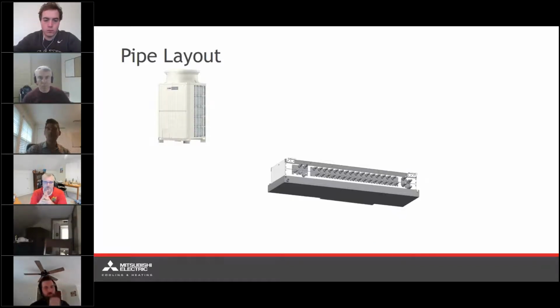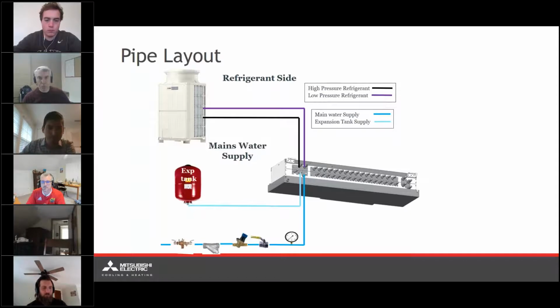All right, so this is just going to go through some of the components that need to be installed on the HVRF system. Again, we have water loops, so there are going to be some additional components that aren't on a traditional VRF. So we're going to need an expansion tank at each HBC controller. We have a filling loop, Cat 3, Cat 4, strainer on each HBC controller. Pressure reducing valve, isolation valves, and that's going to be for all branches, as well as pressure gauges. Again, the more of these we can get onto the system, the better, but ultimately, off of the main water supply, we're going to be wanting these particular components.